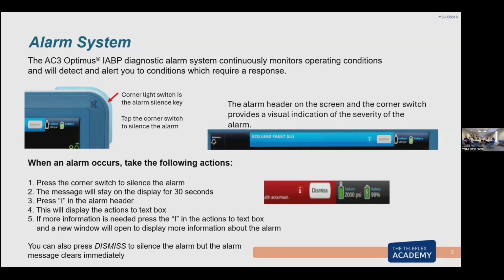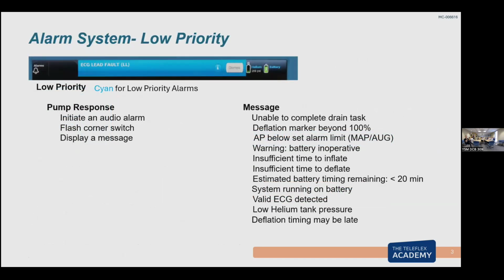Our medium alarm is a yellow alarm. The pump is going to be beeping at you and giving you information about the alarm. Usually I see the yellow alarm come up when we are in standby too long. We pause the balloon pump to listen to the heart and lungs and check out the patient, and we're in standby too long. The high priority alarms are the red alarms, and the pump will stop pumping. It will give you an audible tone and troubleshooting, but the pump stops pumping. This would be similar to your older pump with your kink line and gas loss. For those two alarms, the pump would stop pumping and you had to do your troubleshooting. We will provide the troubleshooting on the screen.